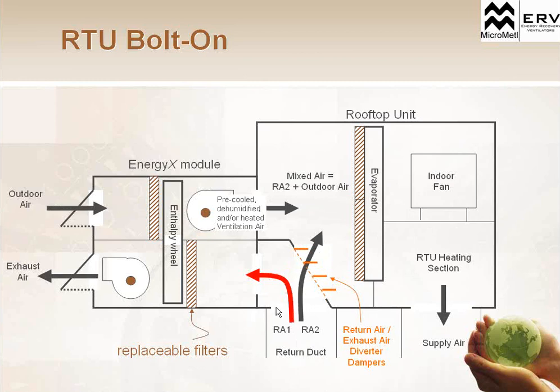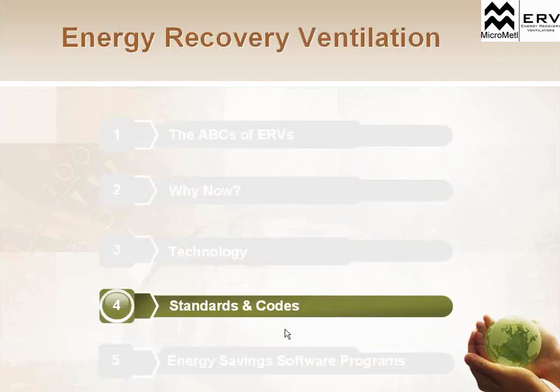We've got return air from the space, either going directly into the unit itself, or depending on the mix of return air CFM and exhaust CFM, we can bring that back through the wheel, out exhausted into the outside air. So we've got the exhausted air coming through the ducting into the unit, out the exhaust of the rooftop unit through the ERV, and then that fresh air coming in across the ERV into the rooftop unit itself. So you're still getting that mixing based on how much CFM you're exhausting. You'll still get that air mixing in the system directly in the rooftop unit.